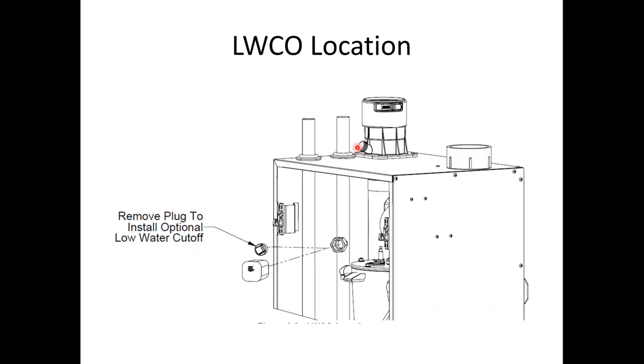The unit does not come with a low water cutoff. There's a plug inside of the unit, and the harness is going to be attached to the supply sensor. You'll see a bundle with red and gray wires, and in that bundle will be the blue and yellow harness for the low water cutoff. Any 4-pin low water cutoff, whether it be Hydrolevel, Guard Dog, Taco, any of those will work as long as it's a 24-volt 4-pin low water cutoff. You pull the brass plug out and screw the low water cutoff into the fitting.